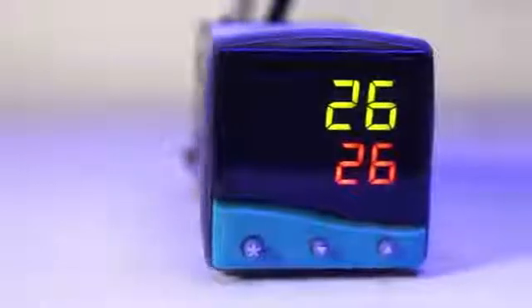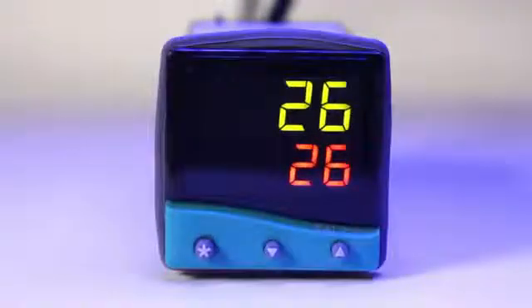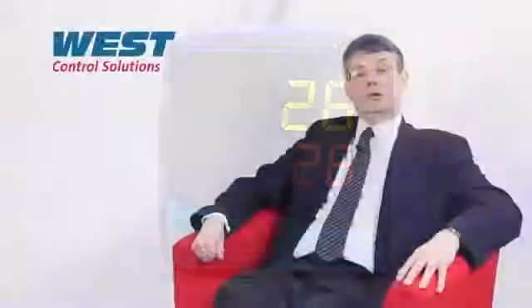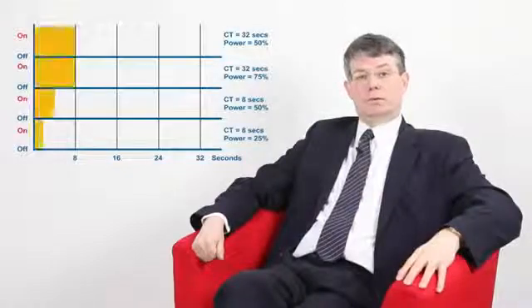There are some processes where it is not appropriate to use proportional control. For example, if you have a refrigerator and you're switching the compressor, you would have to use on-off control. A compressor cannot be turned on and off frequently, as would happen with proportional control. Even if the cycle time was set long, it would still switch more often than would be desired.